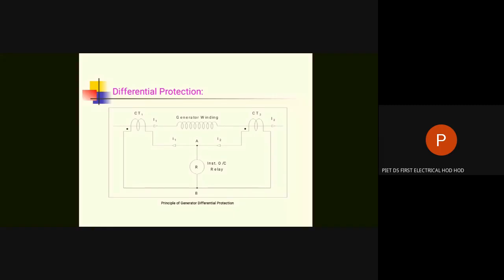Another reason is ventilation system failure. I was telling you that 9050 ampere is for a 210 megawatt generator. Nowadays, 210 megawatt is comparatively a smaller capacity. You might know that at the Wanakbori thermal power plant, there are 7 units of 210 megawatt each, and the 8th unit is of 800 megawatt capacity, a single unit. So 800 and 1200 megawatt are the modern capacities. If I talk about 500 megawatt capacity, the rated normal current is 17,000 amperes. 17 kiloampere is the rated normal current.